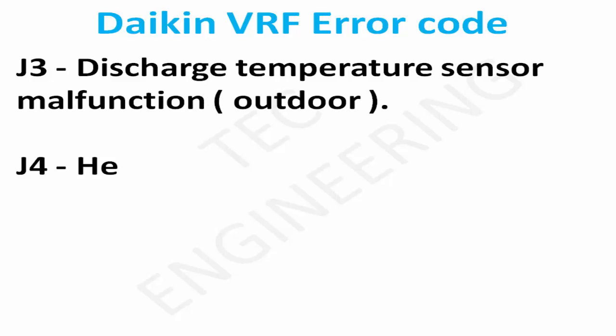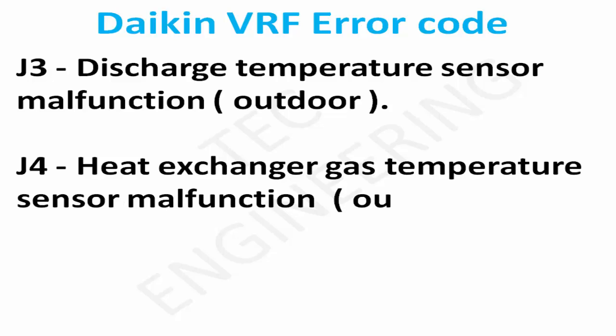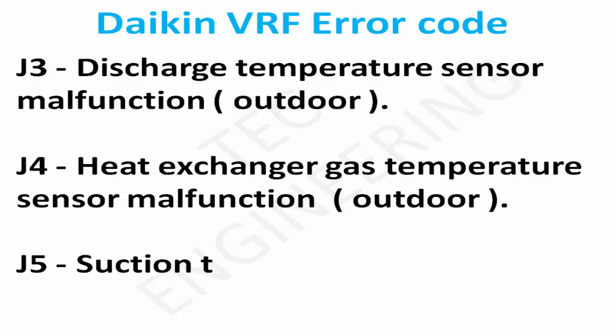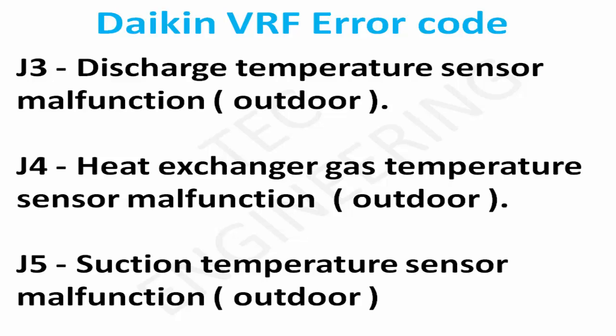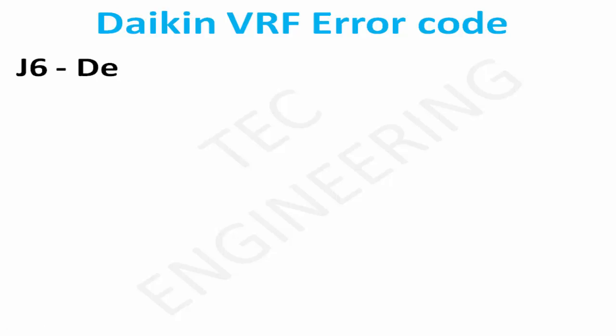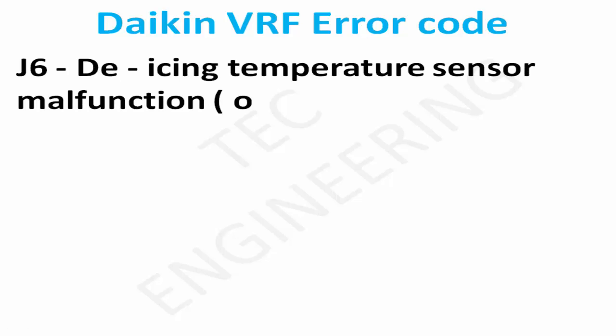J4: Heat exchanger gas temperature sensor malfunction, outdoor. J5: Suction temperature sensor malfunction, outdoor. J6: De-icing temperature sensor malfunction, outdoor.